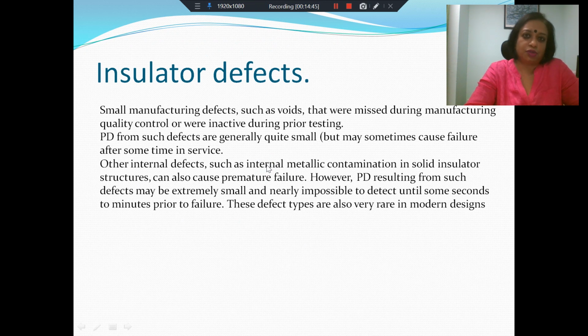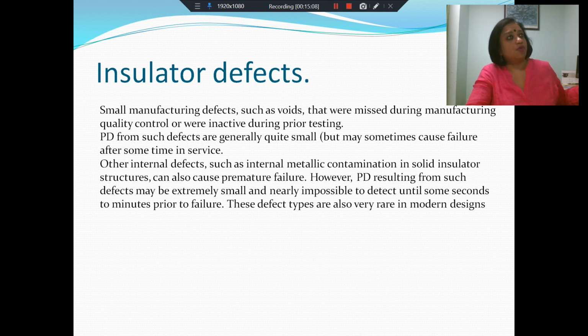Apart from that, we also have insulator defects, where you have small manufacturing defects which probably were not observed during quality control. Even in preliminary testing, they did not cause problems. This could be voids or embedded metallic particles. Generally, the partial discharges from such defects will be small. However, over a long time in service, they can cause failure. But they are difficult to trace at the stage where we can take corrective action.